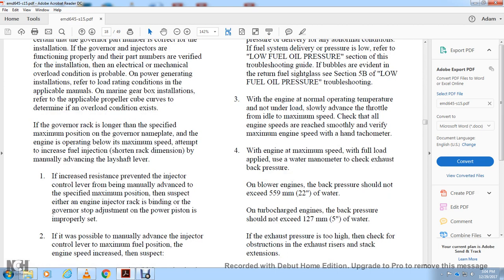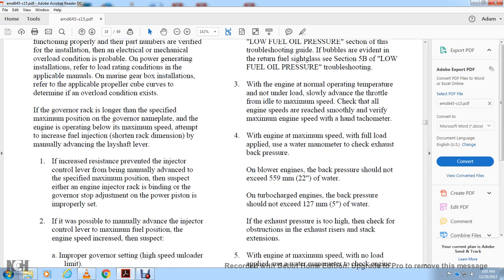If the governor rack is longer than the specified maximum position and the engine is operating below maximum speed, attempt to increase fuel injection by shortening the rack dimension — manually advance the layshaft lever. If resistance prevents the injector control lever from advancing to the specified maximum position, suspect either engine injector rack binding, an improperly set governor stop adjustment on the power piston, or inability to advance the injector control lever to maximum fuel position.